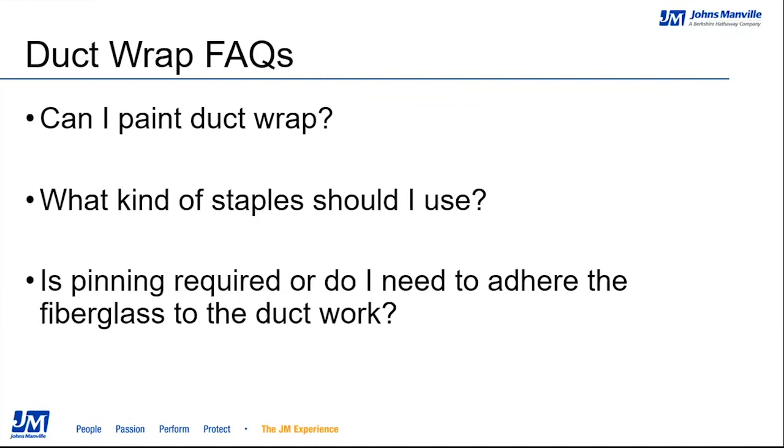The performance characteristics of the duct wrap are really expected to remain constant for the life of the products. But if you decide you're going to paint it for any reason, we don't test or evaluate any of the paints that might be used on the impact of the ASTM E84 surface burning test.